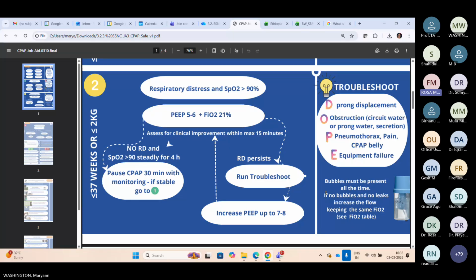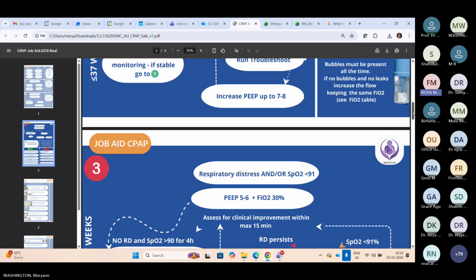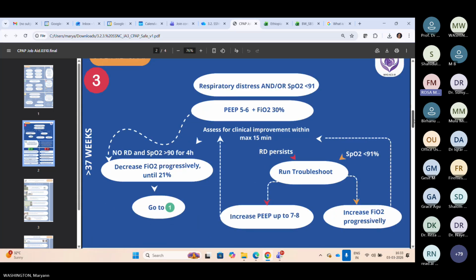Just remember that for babies with bubble CPAP, we need to have bubbles present all the time, and this is also part of the assessments that we ask the SSNC leads to do. If there are no bubbles and no leaks, we can increase the flow until we have bubbles appearing. Also, always remember the water level must be at the level recommended by the manufacturer. So if troubleshoot is run and there are no issues with the DOPE, we increase the PEEP up to 7 and 8, and then we go back up again.